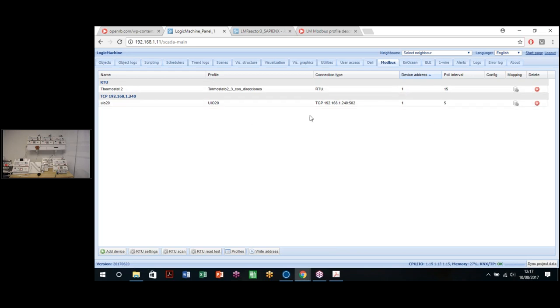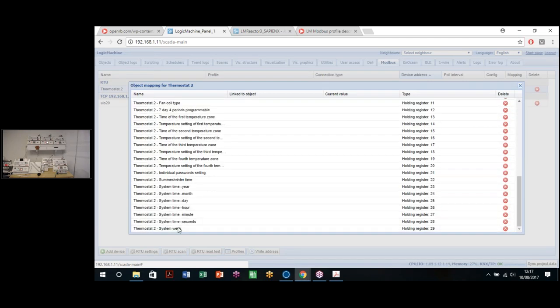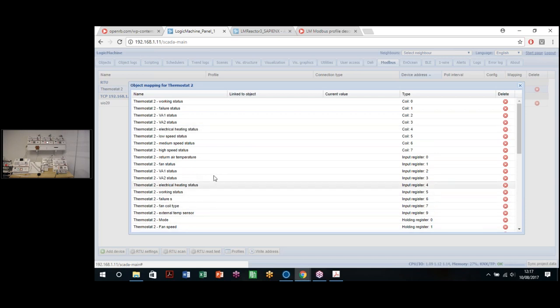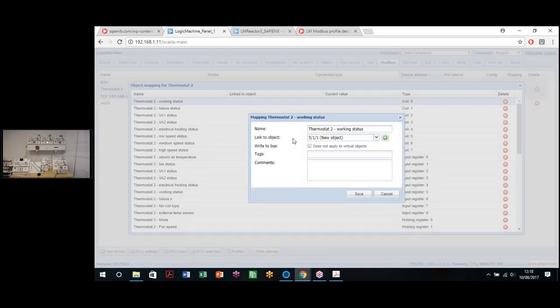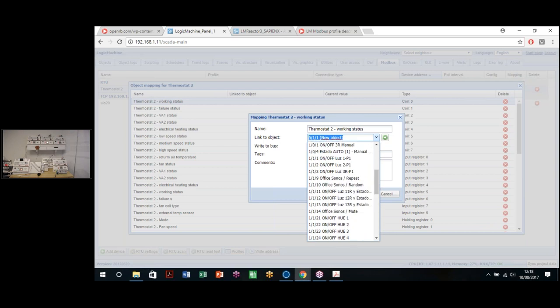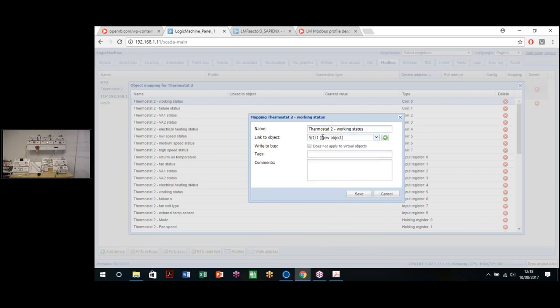Okay, once we have added our device, we're going to do the mapping. The mapping is just the assignment of these registers that we have set with the profile file to the specific object that we're going to control this device with. For that, we click on the mapping button. When we click on the mapping button, it will show all the objects that we have created in the profile file. To link this register with the object that we're using, we just click on it, and it will ask to give a name and a new object. In this case, I have it in the 5. Okay, let's set it that way.